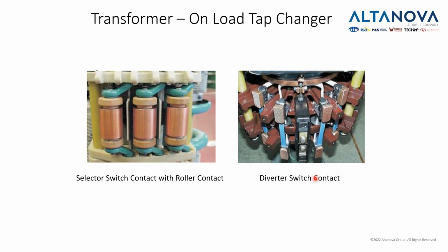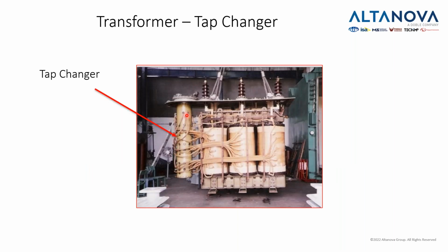What is important to notice is that on these contacts, after a lot of movements and changes of position, you can get some, let's say, patina. It can become dirty, and then the resistance can increase. So that's one thing we will measure. This should be nice and clean, but it's not always like that. That's the reason why sometimes the tap changer needs to be cleaned.